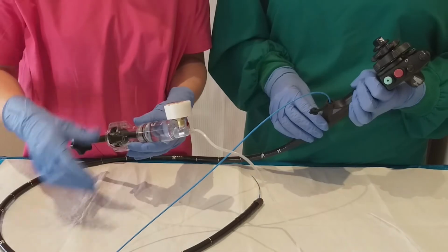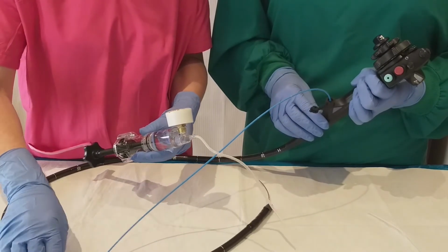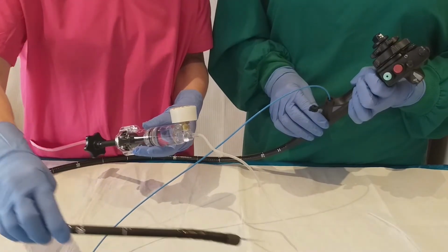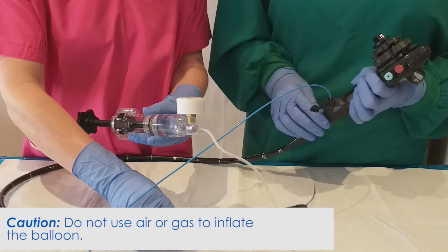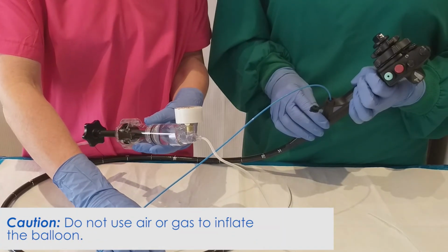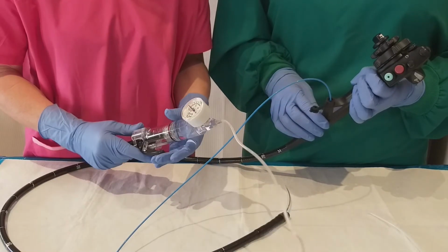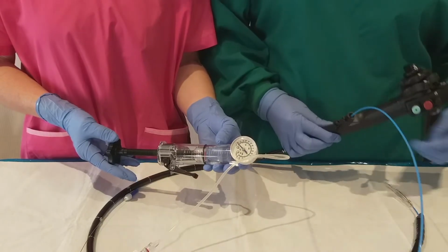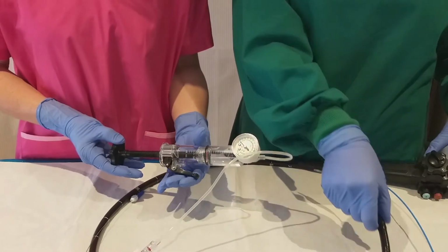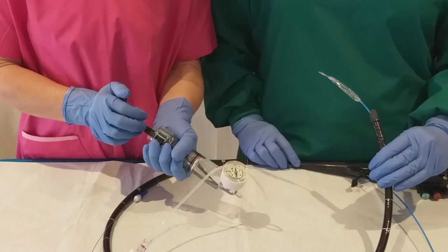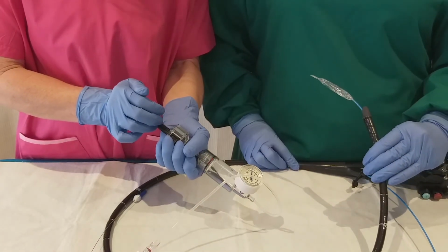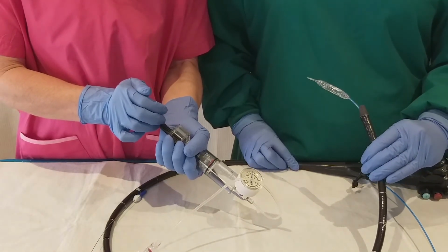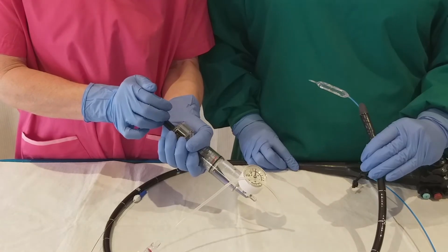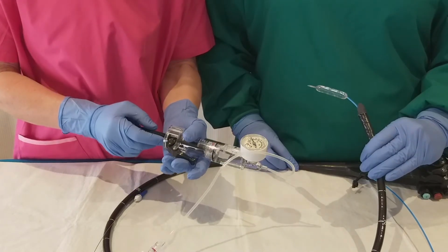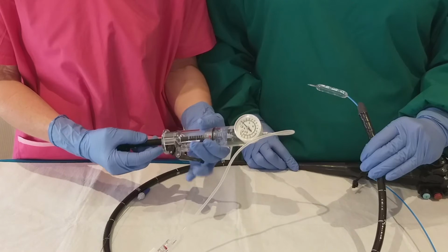Once the balloon's position is confirmed, it is now time to inflate the balloon using the inflation device. Caution: do not use air or gas to inflate the balloon. When instructed by the doctor, squeeze the lever and push the plunger forward to inflate the balloon. Make sure the syringe is facing downwards to make inflation quicker. Release the lever once you have injected fluid into the balloon.